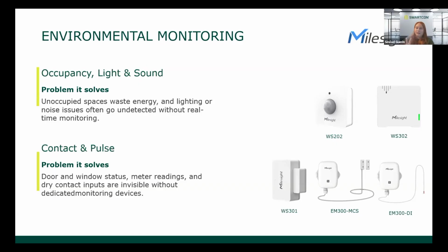The EM300 DI is a really nifty device. It's a pulse counter, so if you have a demarc point from any of your meters, you can tie this in. We utilize it with water, gas, and electricity to get visibility into those meters without replacing them. We've also used it tied into any dry contact, like generators or alarm systems that don't connect to the building's BMS but have a dry contact output that triggers a change in status. That can trigger the pulse counter and give us an alarm on our end, a unique way of utilizing these sensors.